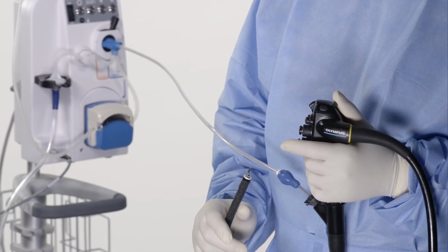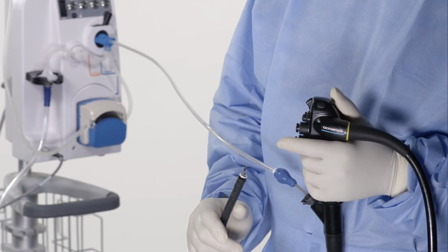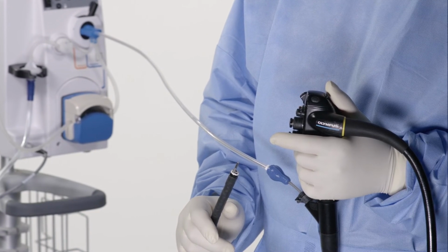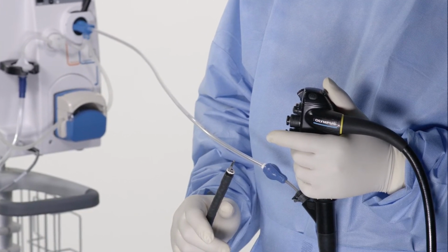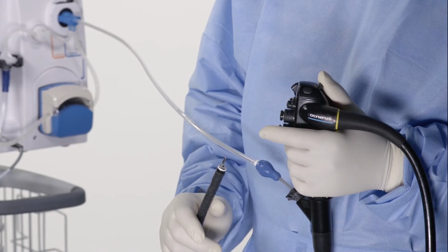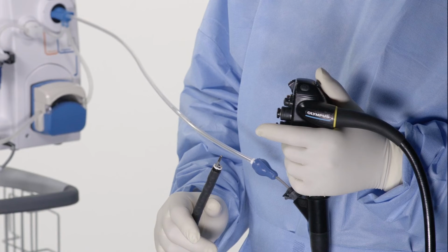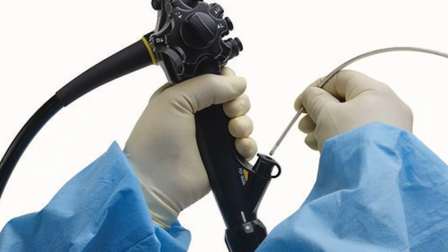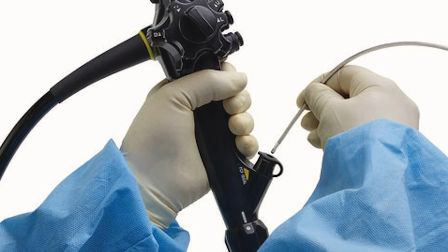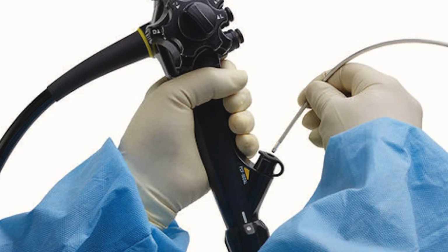Maintain sufficient distance from the console so that the flexible outer tubing is as straight as possible with no kinks or coils. Failure to do so may affect performance. If performance is affected, then straighten the outer tubing and operate the device. The angle of the catheter should be no greater than 90 degrees when entering the working channel of the endoscope.